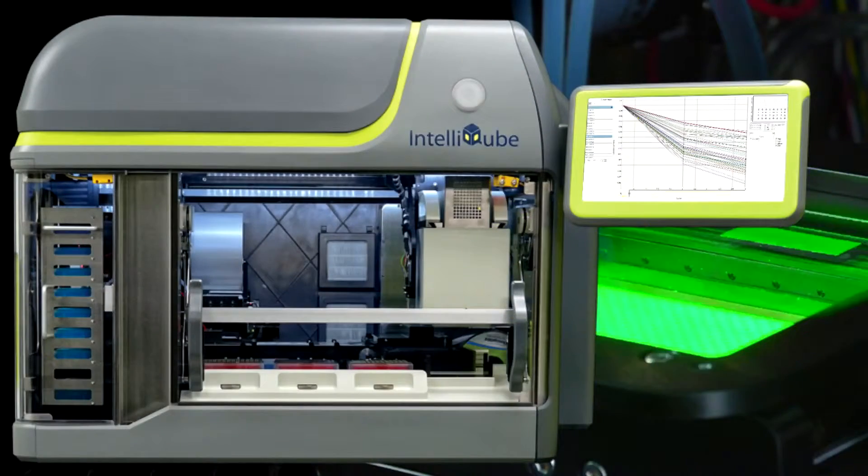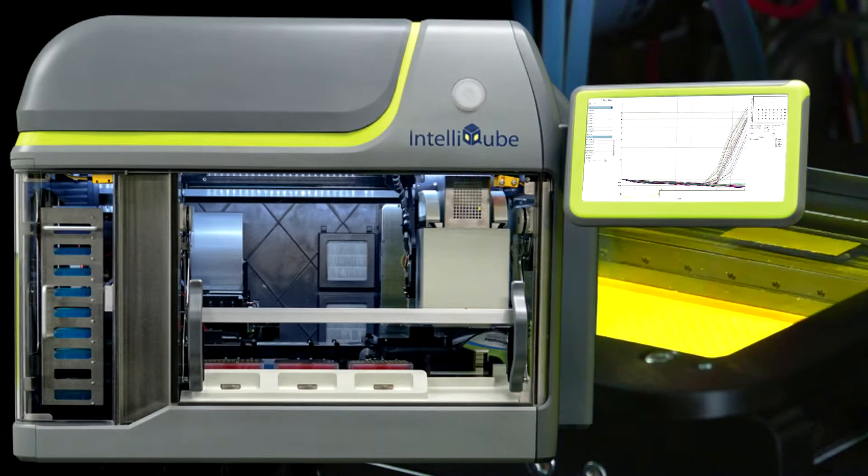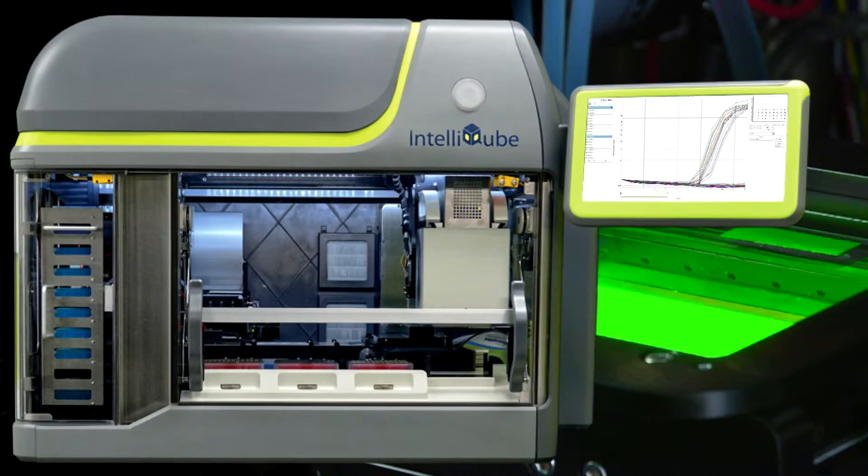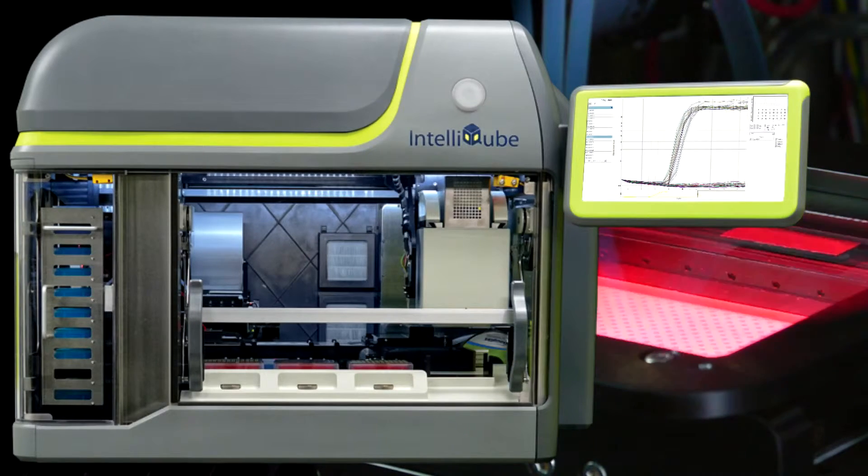The IntelliQube software supports protocol generation and subsequent data analysis of PCR results. Lab personnel can observe amplification curves on the instrument in real time.